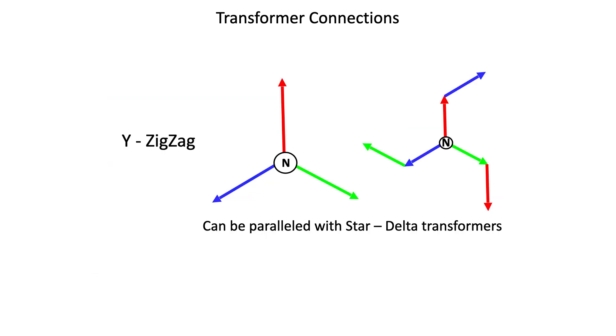The benefit from converting an older transformer station from a Y-delta to a Y-zigzag transformer set was the fact that the secondary phase to phase voltages were shifted 30 degrees from the primary phase to phase voltages, thereby matching the previous Y-delta transformer.